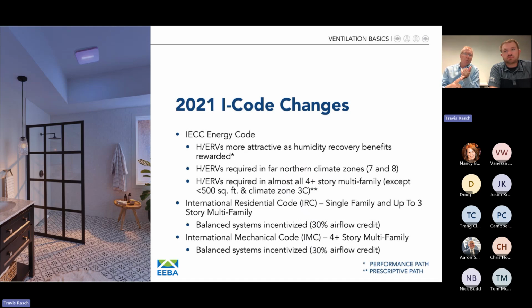So with each energy code update, and I should mention the 2024 codes are out there now, next year, 2025, we'll start to see states adopt that, and that has even more stringent energy requirements. But ERVs are now required in single family climate zone 7 and 8. When it comes to the 2024 version that just was put out there, they're going to add climate zone 6 to that. So ERV requirements keep working their way south from the most northern climate zones. They're realizing more and more often that they're going to pay themselves back with good, efficient, fresh air. And on the multifamily side, if any of you are involved in multifamily, for 4+ story high rise, prescriptive path now requires ERVs. So again, with each passing year, the codes are more and more requiring or incentivizing ERVs.